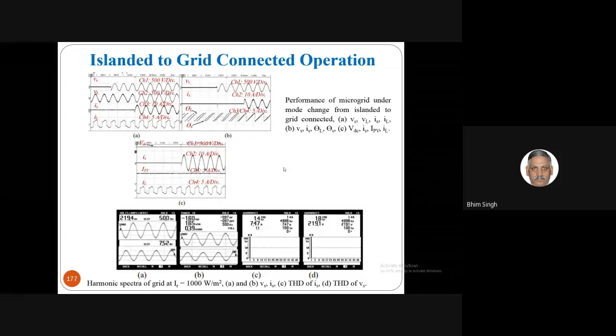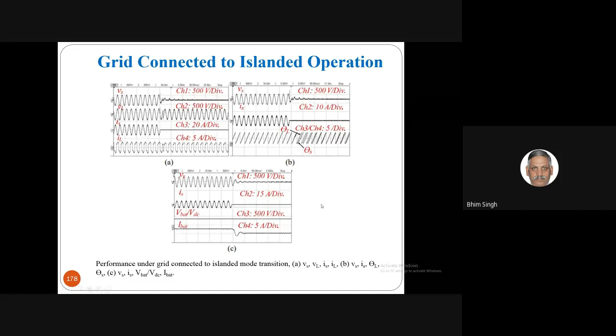For synchronization, we couldn't find any literature. Initially one or two students blew some devices, but after that I told them to be cautious and do it in proper simulation first. So we go on adding these features, because in practice you have to synchronize this total system to the grid, not only look at the behavior of your control for the purpose of compensation. And you can clearly see the load is not affected when the grid disappears. Load voltage and load current remain there.